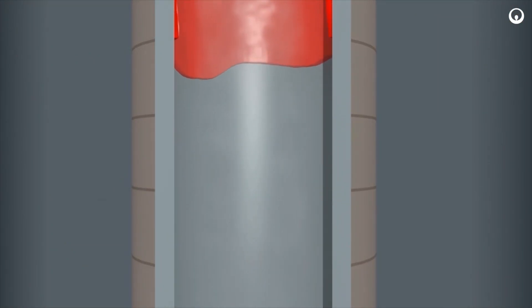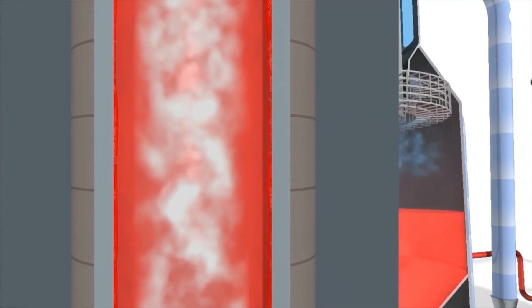The liquid flows down the tubes coating the inside wall as a thin film within each tube. As the liquid flows down the tube, a portion of the brine evaporates and produces steam. Both the liquid brine and vapor are flowing in the same direction.